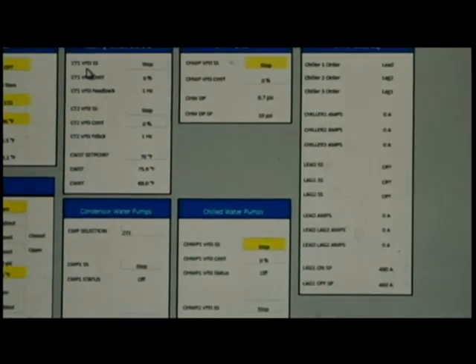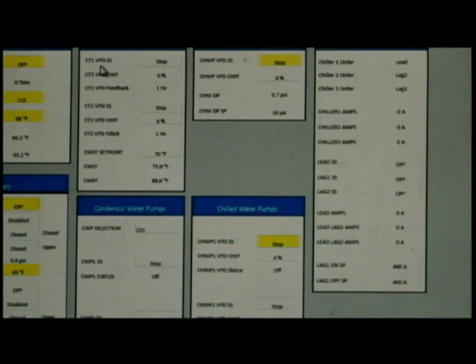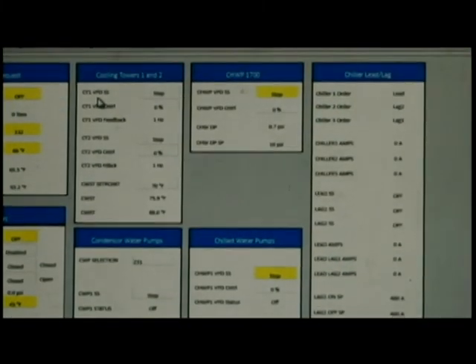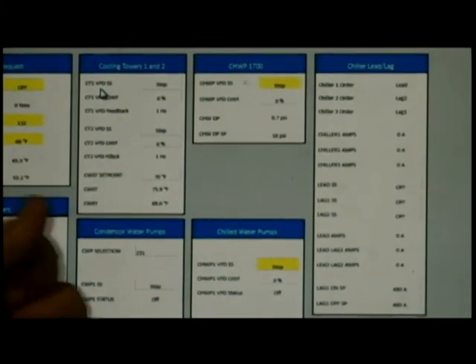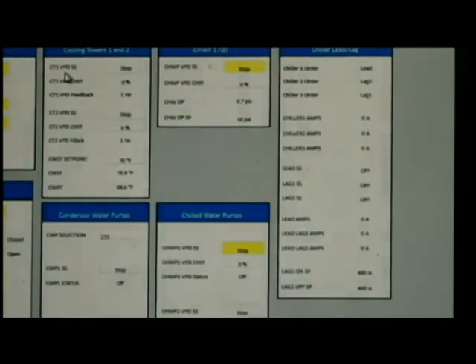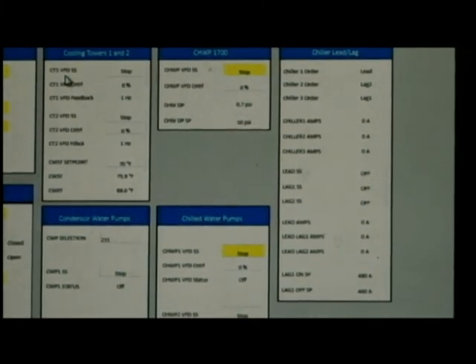Right underneath it is where we monitor the amps coming back from the unit. This is where we are getting information from these chillers via their BACnet interface. They give us a percentage of load that they're running. We calculate that amperage based on the nameplate full load amps for each chiller, and we multiply out that percentage and get the amps that the chiller is running at. So we report chiller one, two, and three amps. And then just like on the other systems, you have your lead, lag one, lag two, start, stop flags to tell you what state your system's in if we're trying to run one chiller, two chillers, or three.